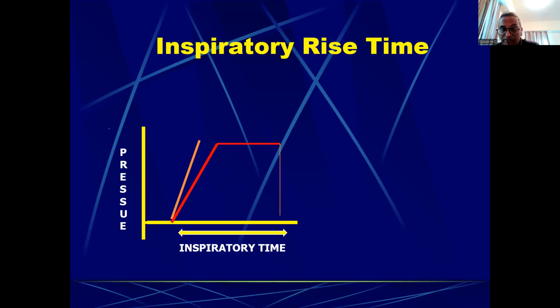If by mistake somebody goes into the system and changes it to, let us say, 20 or 30%, then the patient may not get enough pressure. So that's why it should not be changed unnecessarily. Usually it is hidden. Since you don't see it, you have to go in there and change it. Sometimes people who are doing it for the first time mistake this for inspiratory time. This is not inspiratory time. This is inspiratory rise time. For example, if you put inspiratory rise time as 1 second, that will be quite disastrous for the patient because you won't get enough flow, right?